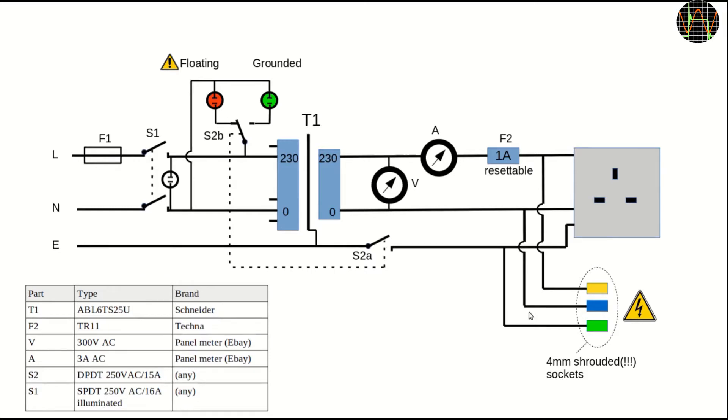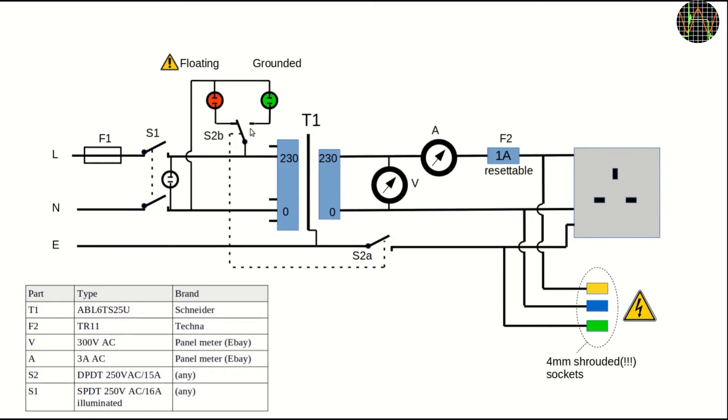It is important for your safety to use shrouded sockets here to prevent an accidental touch. Switch S2A allows to disconnect mains earth from the output, making it floating. This is the main purpose of the isolation transformer, but it is a dangerous setting, so you need to know what you are doing and what the consequences could be. As a reminder for myself, I use a second set of contacts on that switch to illuminate two neon lights showing which setting is currently used.